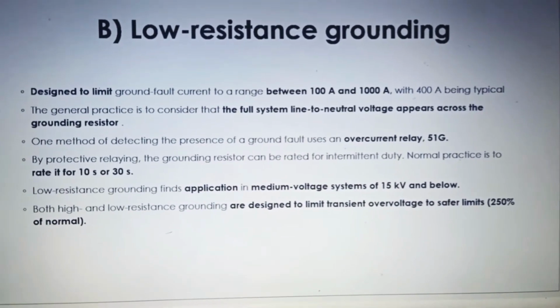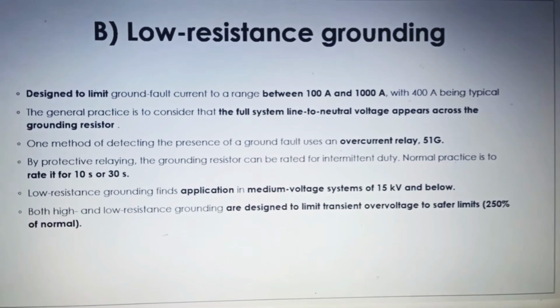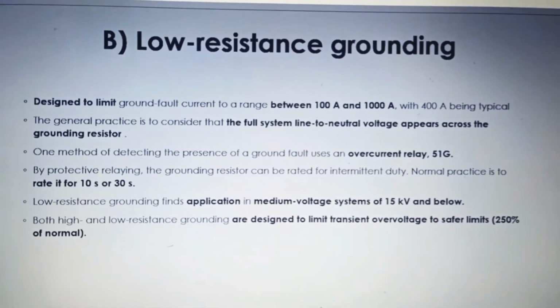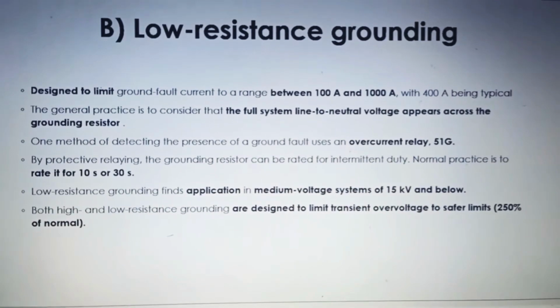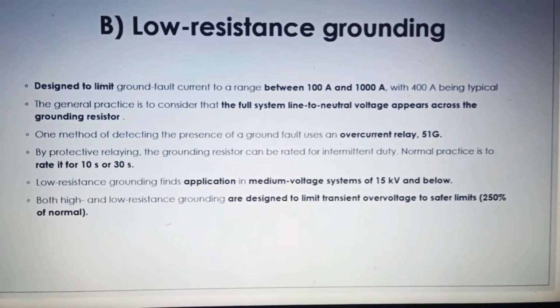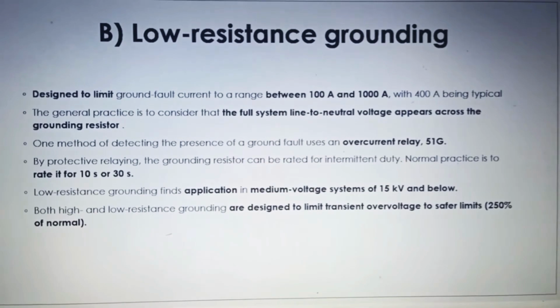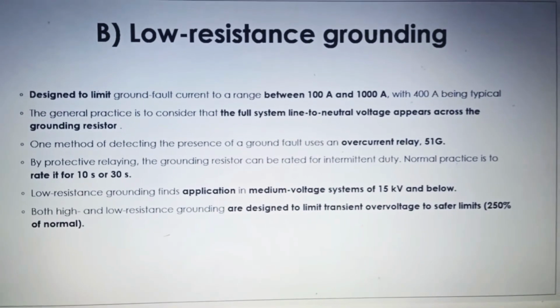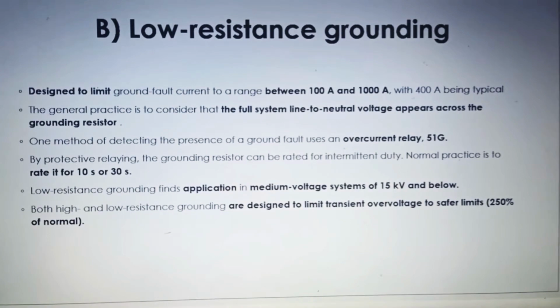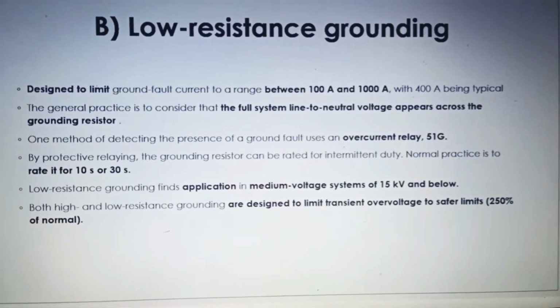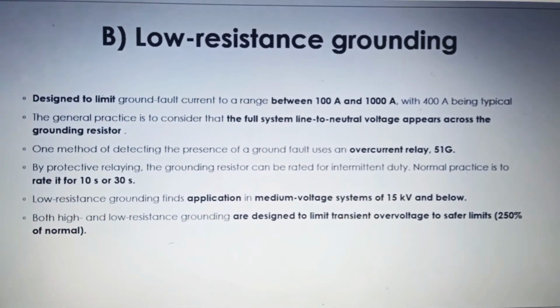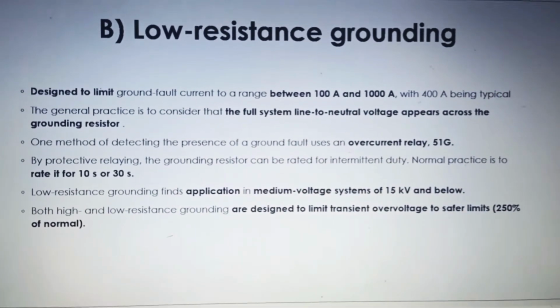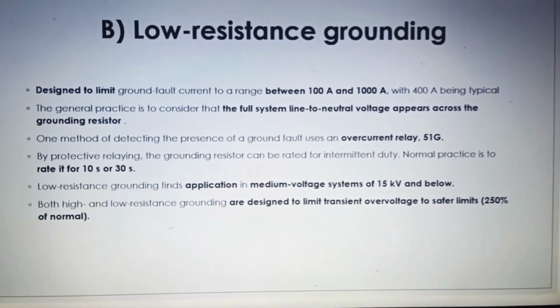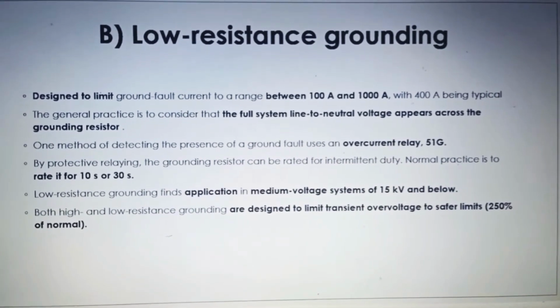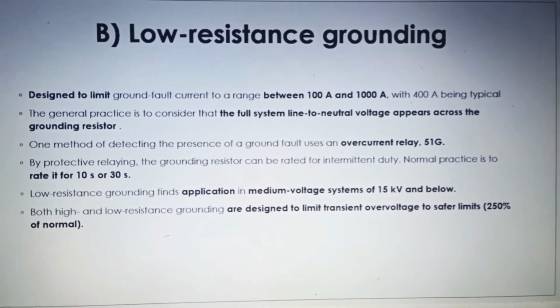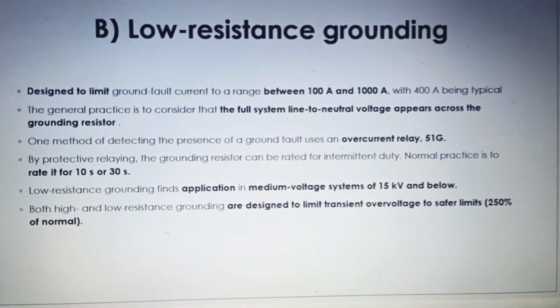Since it is the intent that the ground fault current supplied by low resistance grounding be promptly and automatically cleared by protective relaying, the grounding resistor can be rated for intermittent duty. Normal practice is to rate it for 10 seconds or 30 seconds, depending on the degree of security appropriate to the application. In cases of fault that are not or cannot be disconnected by the secondary breaker, the ability for prompt and automatic disconnection of the primary source is required.